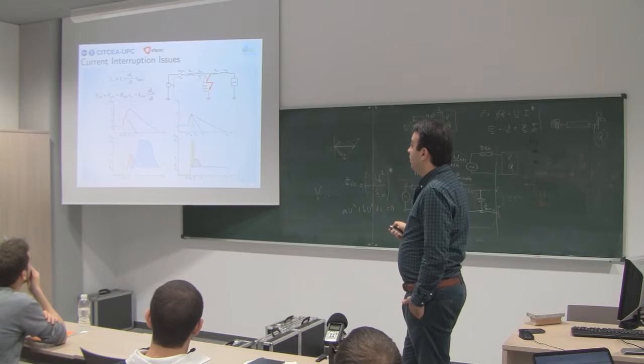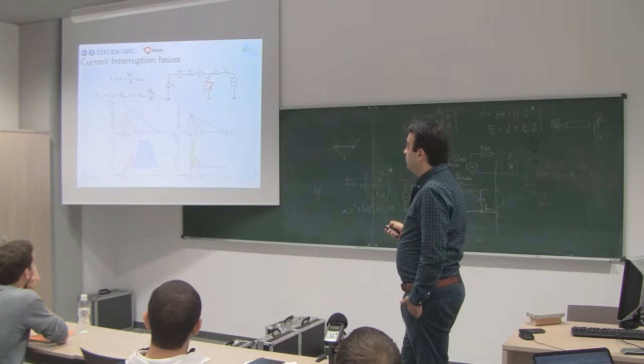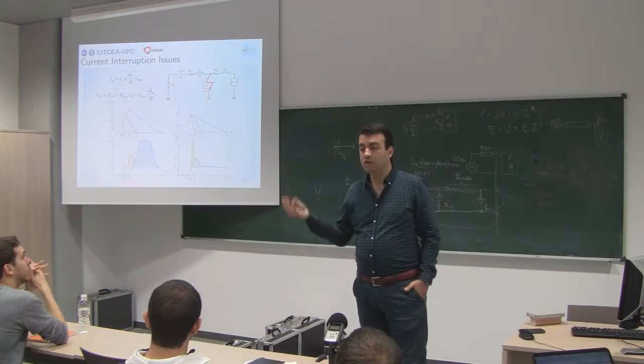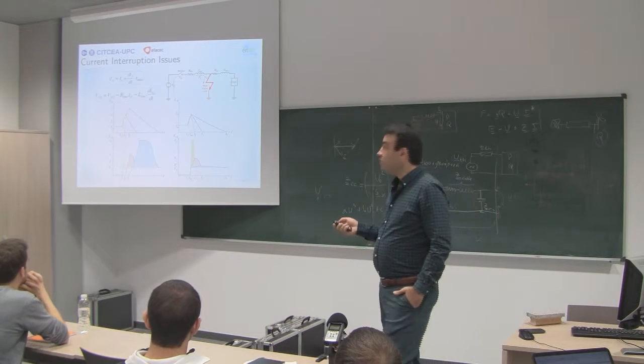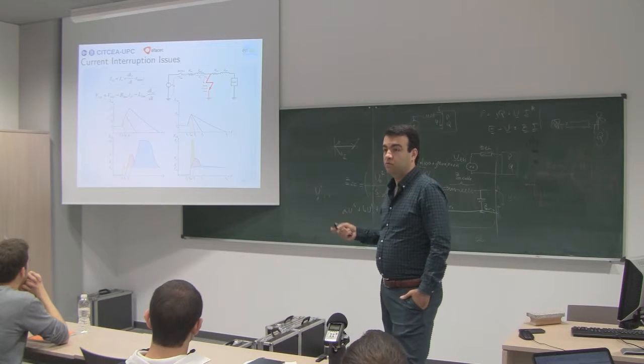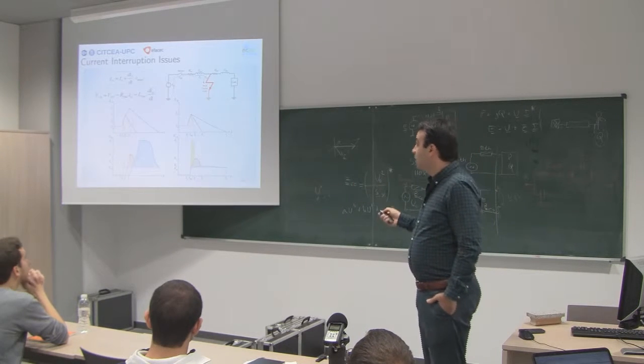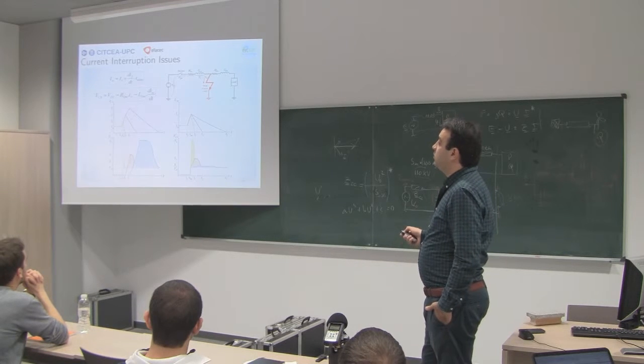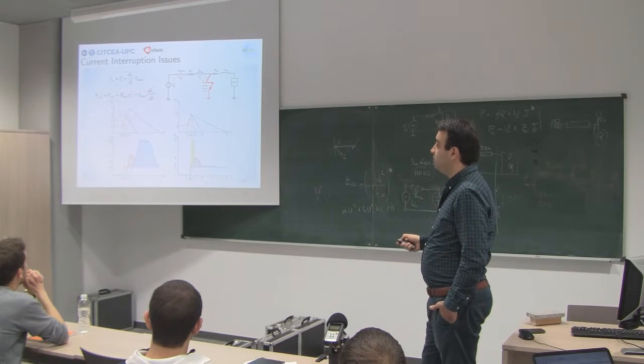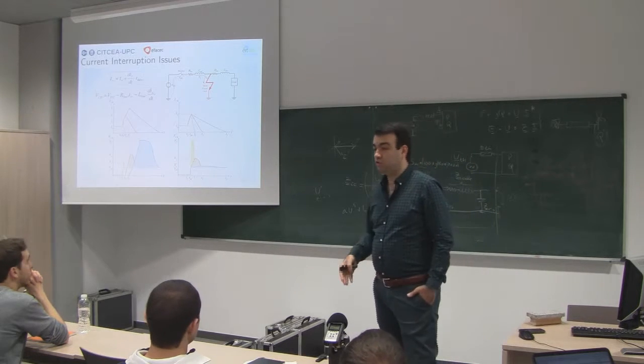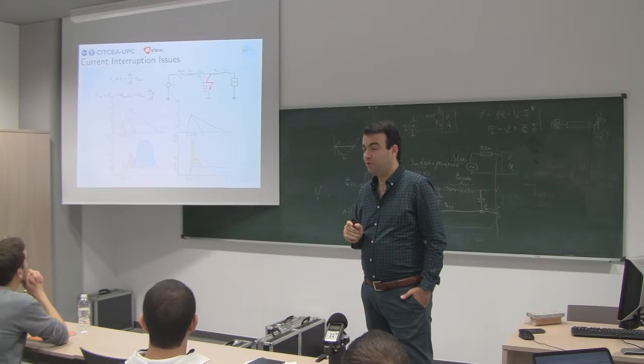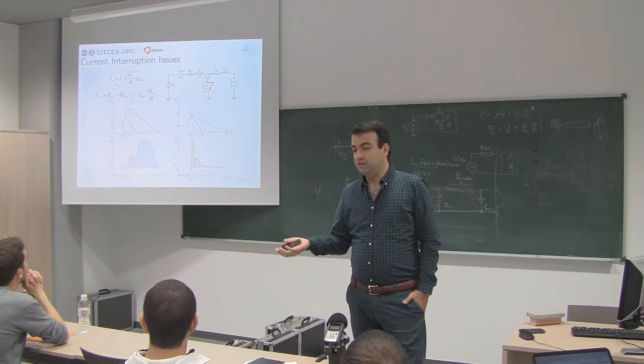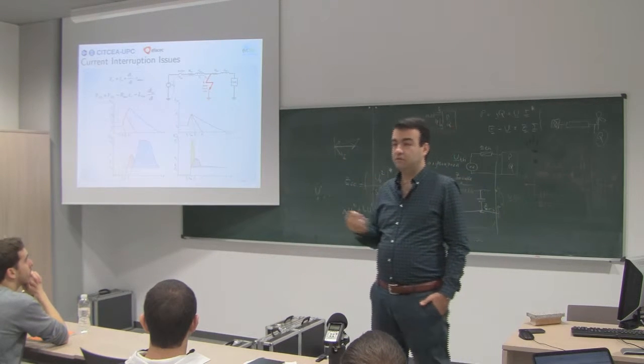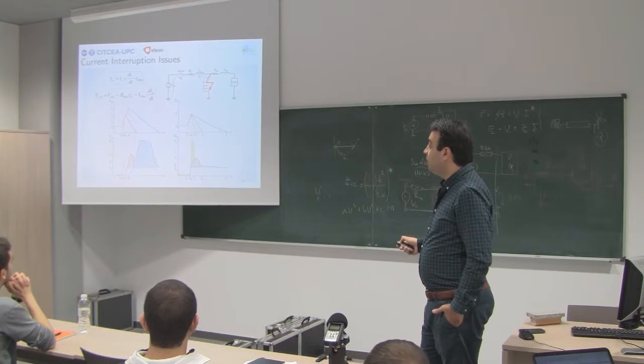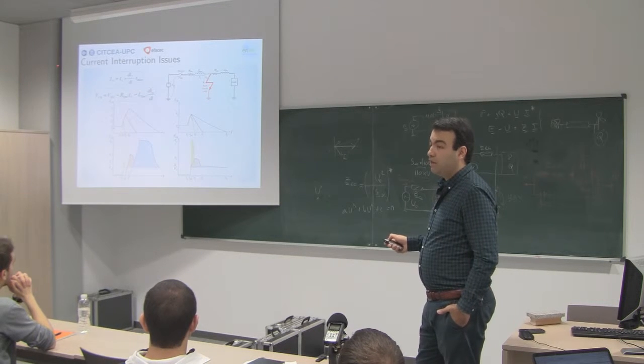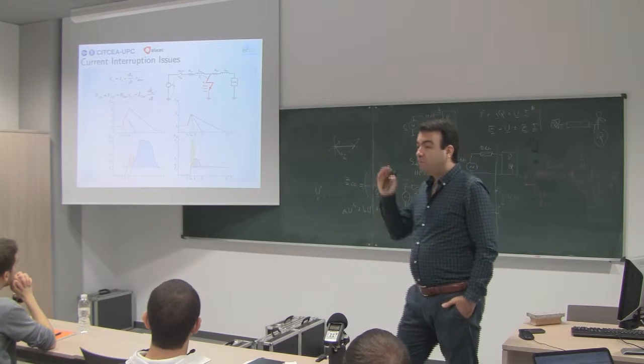Suppose this circuit, this is a simple demonstration of a DC source and a load, connected through these impedances, which are supposed to be like a DC line, a simple model which has a resistance and inductance. And you want to open this switch, which you can think of as a set of IGBTs. What's happening there, if you write the equations for the short circuit current and also for the voltage across this breaker, you will see that when you try to interrupt this short circuit current within a short period of time, because the IGBTs are so fast, they like to interrupt any current. If you turn them off in less than, you can think, 1 microsecond, even 2 microseconds, you will have a very, very small dt here, and you have a large di here, because we are talking about the short circuit current, and you are pushing the current to become zero.